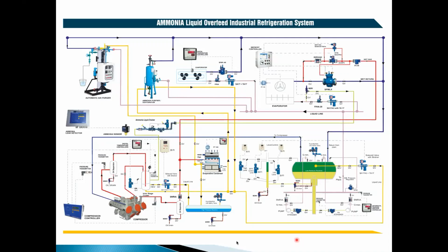What is the difference between a gravity feed system and a liquid overfeed system? If you see this part, the compressor, the condenser, and the receiver are the same. However, the liquid which comes from the receiver goes to the low pressure vessel or the pump recirculator vessel. Here, using this hand expansion, all the expansion devices, the liquid is expanded to the required temperature. Suppose you want to have a freezing point of -40. So your ammonia liquid is expanded here from, say, 12.5 bar pressure to -0.3 bar pressure, and this liquid is accumulated and stored in this vessel at -40.